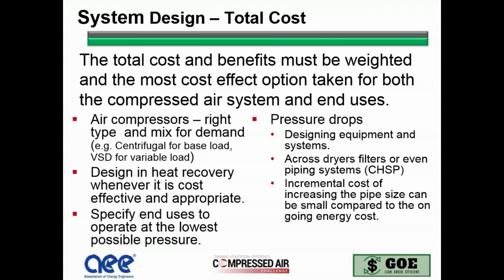So the air compressors themselves, again, the right type and right mix for the demand. You want to make sure that you have good base load units, and you use those for base load, like a centrifugal, and then for variable loads, you'd want to use VSDs as an example. You want to be able to design the heat recovery, which we talked about, whenever it's cost effective and appropriate. You want to specify the end uses and operate at the lowest possible pressure. Again, once you get those big uses down, you can start lowering the pressure in your total system and not let those drive it. And then, of course, pressure drops. Design systems and equipment to minimize pressure drops, whether it's across the filter dryers, even piping systems.